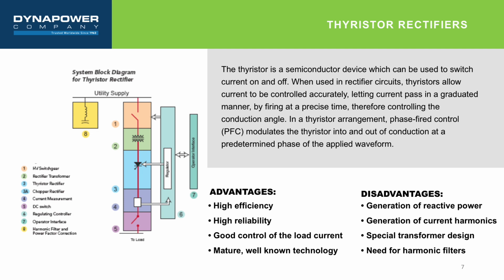Thyristor rectifiers. The Thyristor is a semiconductor device which can be used to switch current on and off. When used in rectifier circuits, Thyristors allow current to be controlled accurately, letting current pass in a graduated manner by firing at a precise time, therefore controlling the conduction angle. In a thyristor arrangement, phase-fired control (PFC) modulates the thyristor into and out of conduction at a predetermined phase of the applied waveform. In general, the main advantages of thyristor rectifiers are high efficiency, high reliability, good control of the load current, and is a mature technology that has been applied for many decades.